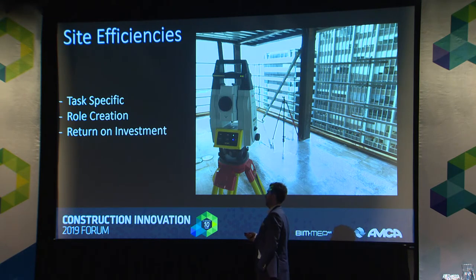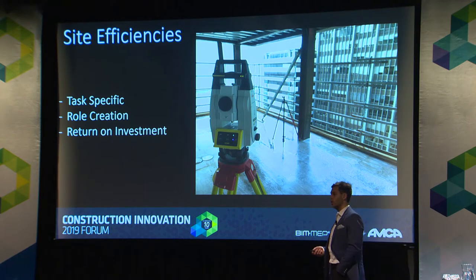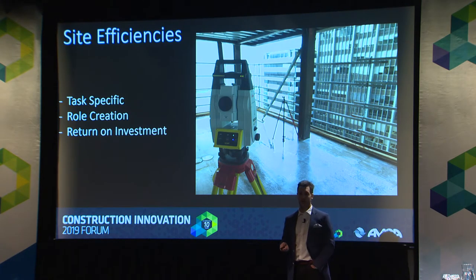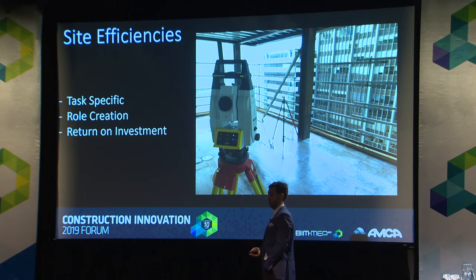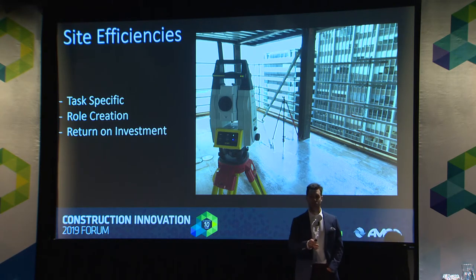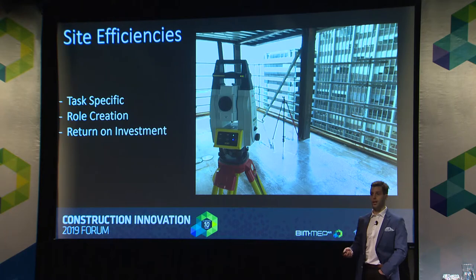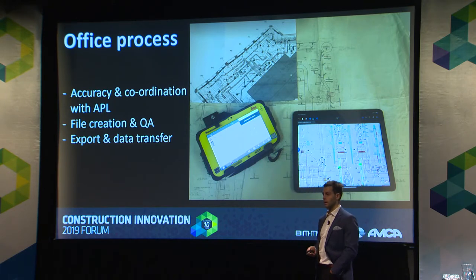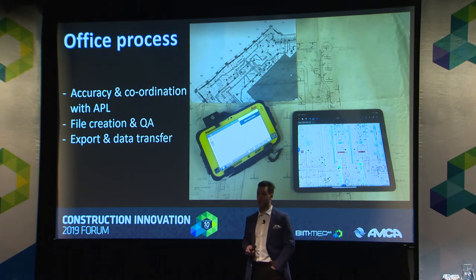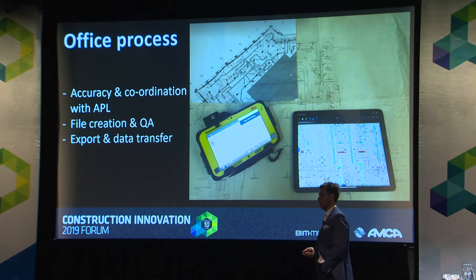This site efficiency has also created a new role within our company — a Construction Technical Lead, which is a plumber who is really interested in technology. They can speak both languages. We now have plumbers utilising Revit in the office, whether doing set-out points or linking point clouds, and they understand the difficulties of office design and software while also being able to talk the same language as the site plumbers. Getting support from CR Kennedy's for this work has been really helpful — they're the experts in surveying. Our office process using the Autodesk Point Layout tool is simple, and the site process — a couple of hours to set out a floor — lets us do multiple floors in a day and move on. A single example: an 80-metre chilled water pipe run. The site estimate was four hours to set out at six to seven metres height off the ground to the purlins. We set it out within an hour and a half using the new tool, and we're not even efficient at it yet.